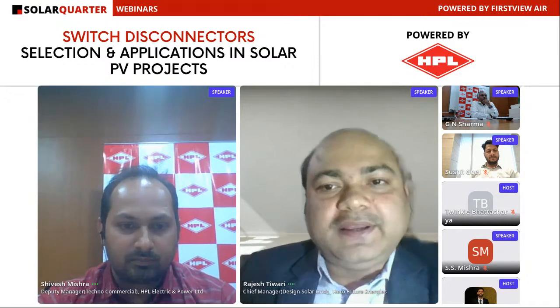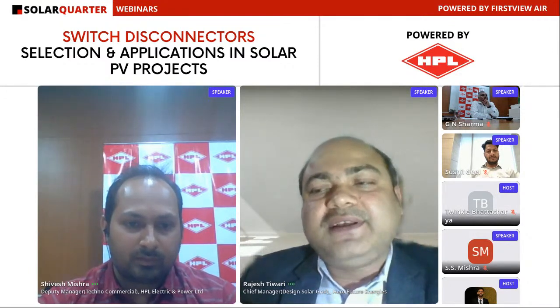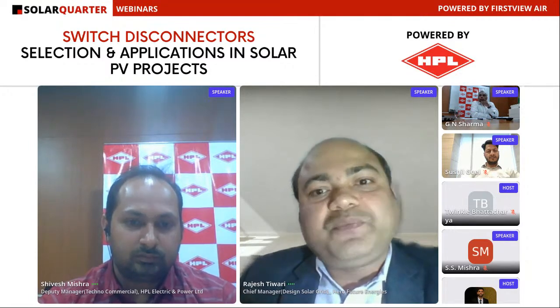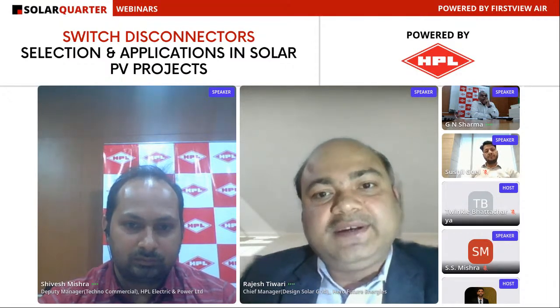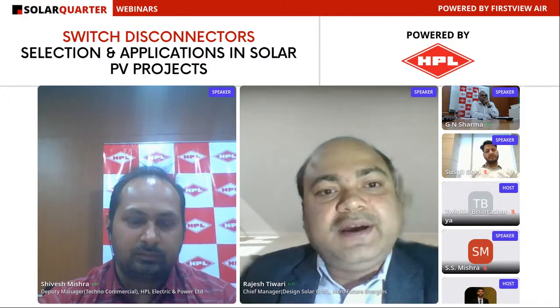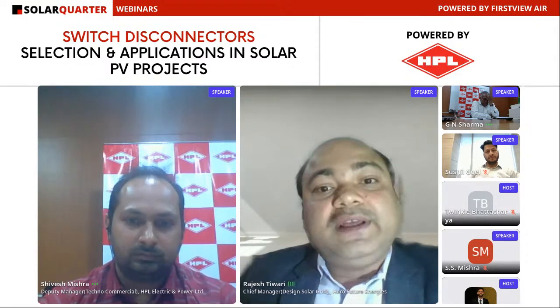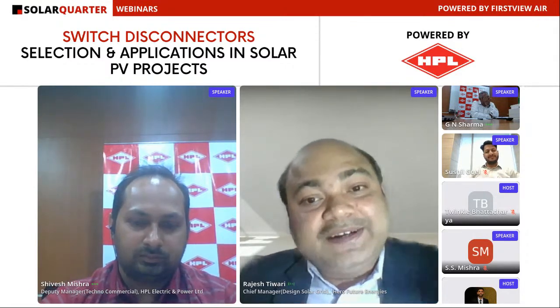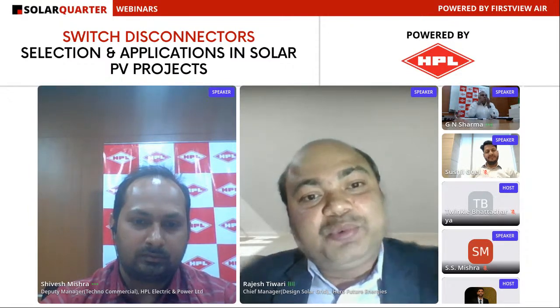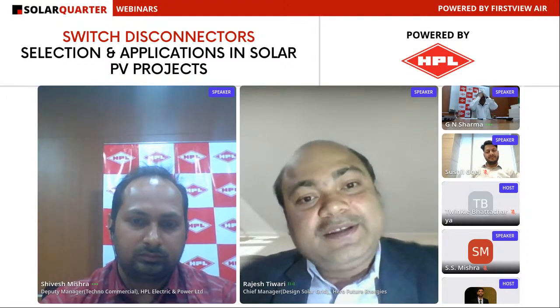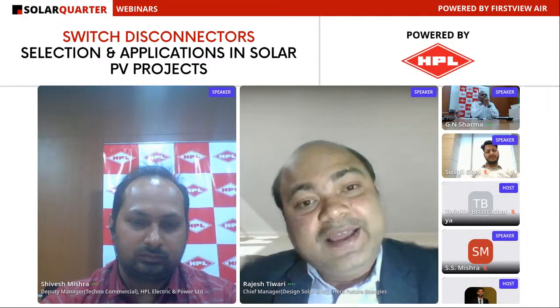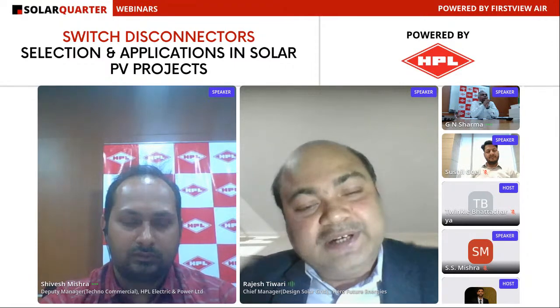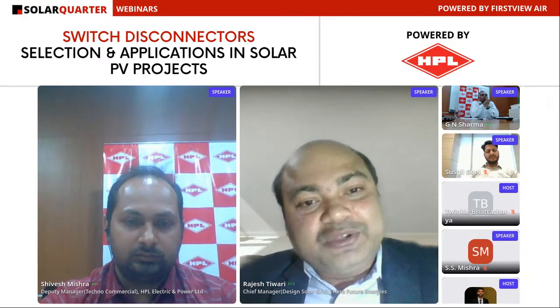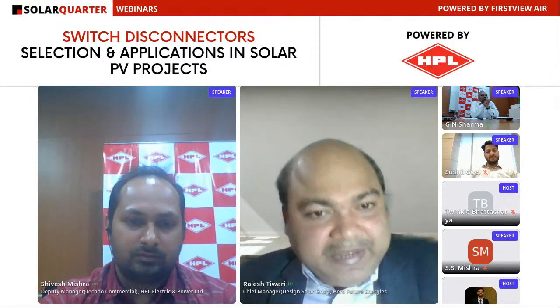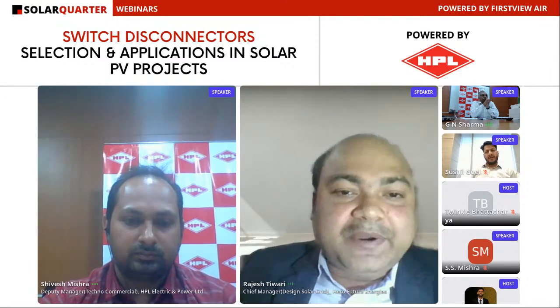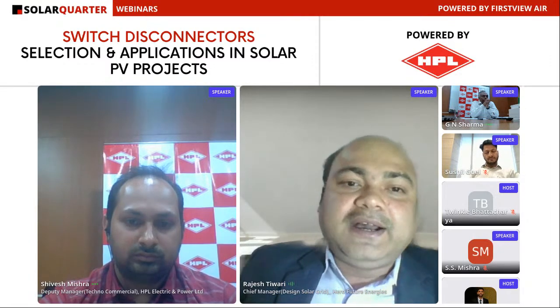Fine. My concern is that as a developer we don't have the facility to measure the actual outside temperature, due to global warming, as the temperature is increasing day by day. Even inverters are designed for different temperatures. Their output is rated at 50 degrees, and then they are capable of injecting 10 or 15% higher at 40 degrees, or 25% higher at 30 degrees. Your inverters are kept inside a shelter, where the temperature may be lower or air can blow, but your LT panels are kept on the platform, and that platform may have a different temperature scenario.